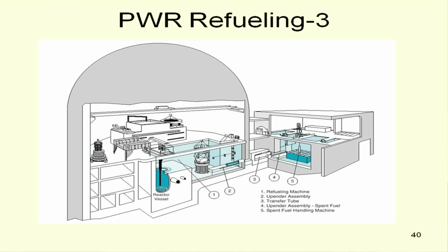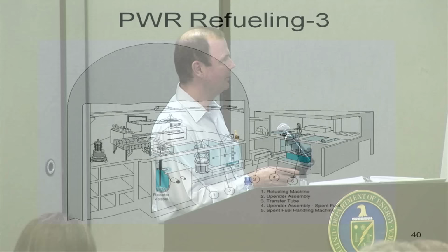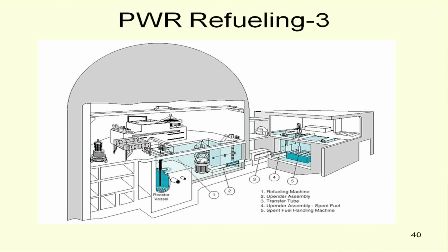A little bit more about how this goes on. You see the reactor here, and the head and the control rod drives have been removed. Normally this entire area up in here is dry. It's just a big pit, and they usually put some kind of a lid here so things don't go into it. But during refueling, after you get the lid off, you flood this entire area up to essentially floor level, and it provides more radiation shielding. Then you take an assembly out and move it over here and set it down, and this little gizmo turns the assembly on its side, from vertical to horizontal, and it goes through a little tunnel out into the spent fuel pool, which is just a big swimming pool where you're going to store it and let the decay heat go away. Then you get it by the handle and drag it upright and put it in a rack, and there it sits. You'll see later the BWRs are a little bit different than that, and maybe in some important ways. But that's how refueling basically proceeds with these things.